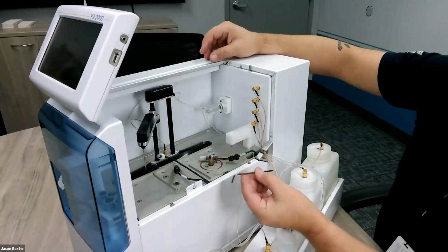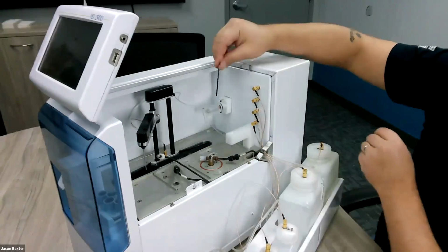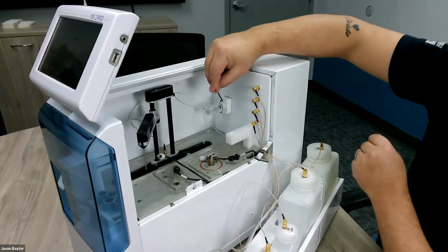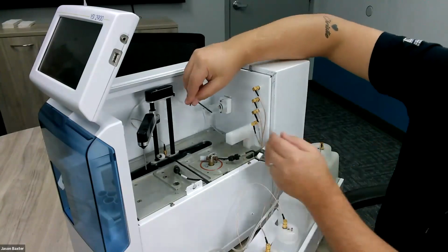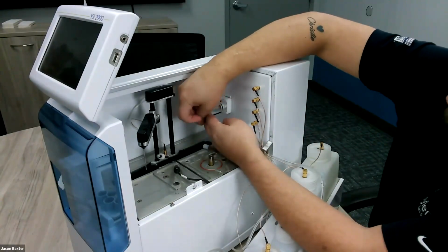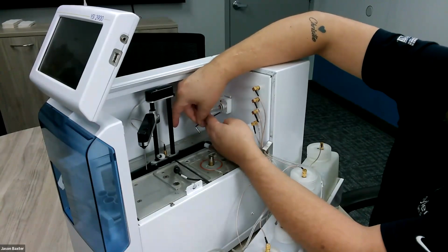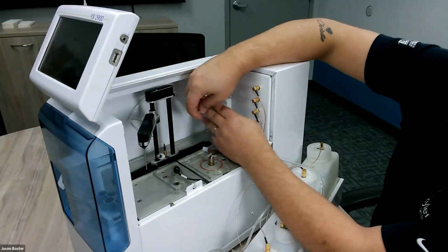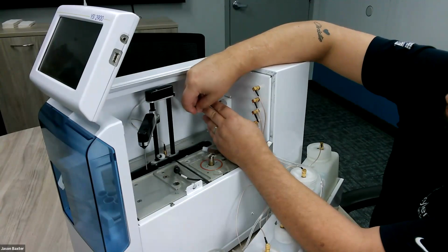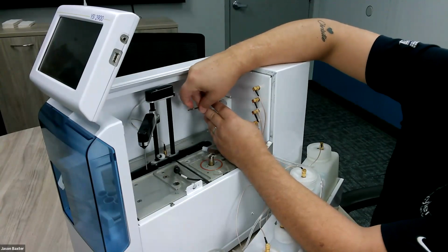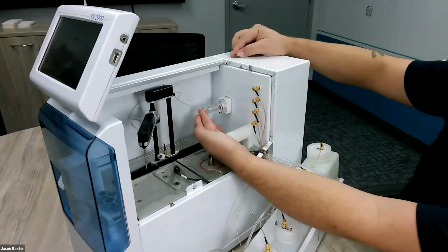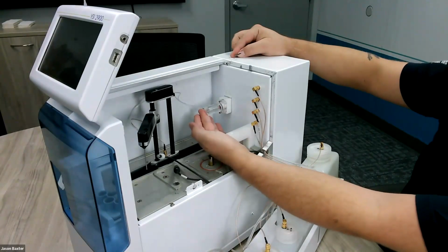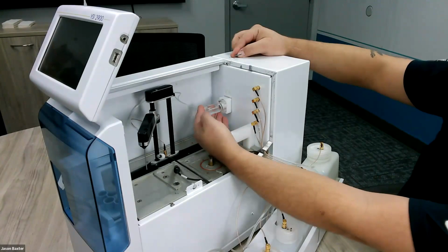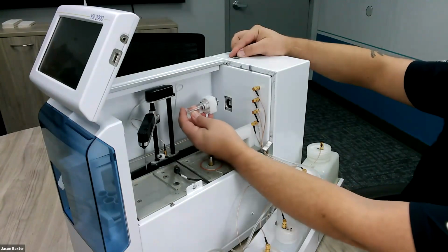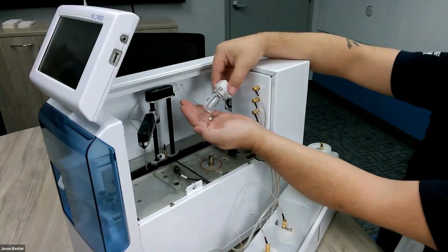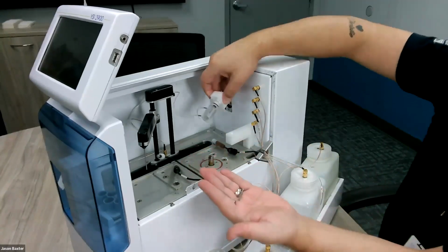Lastly, take your same 3/32 Allen wrench, remove the 2 bolts that hold your sipper pump assembly onto the back wall of the device. Once you have both bolts loosened, the only thing holding this sipper pump assembly onto the device right now is my hand. So you just want to make sure you have your hand ready, so that you can remove this as a cartridge and simply pull it off. Tip it forward to capture your 2 bolts.